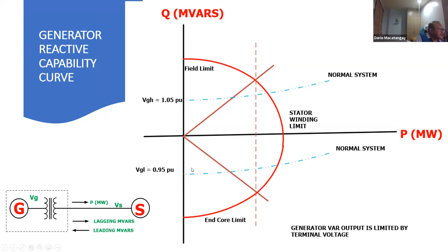Now, when the voltage is low, 95%, this point here is the amount of megavar that can be absorbed by the generator. During daytime, the system would need megavars. You need to support the system with megavars. Otherwise, if the system does not have megavars, with so many loads, so many motors, the system will collapse. So you need megavar support from the generators, from the power plants. So they operate at lagging megavars here.